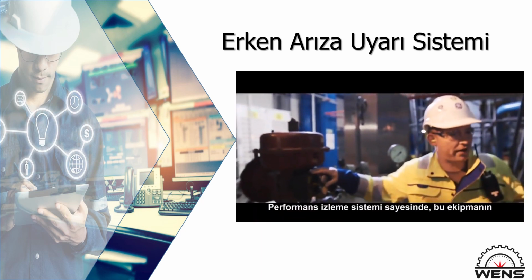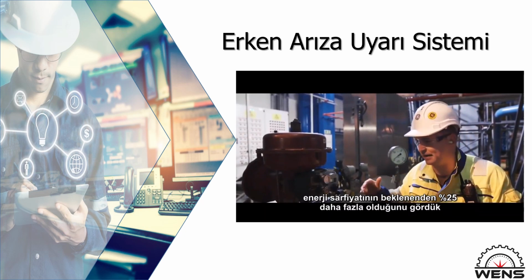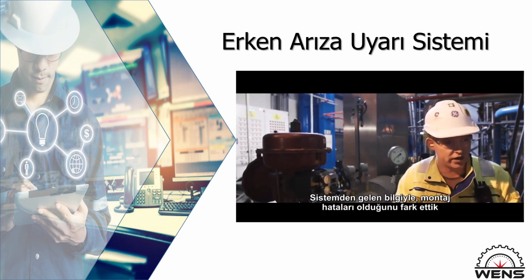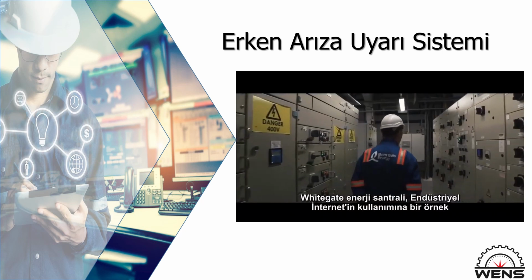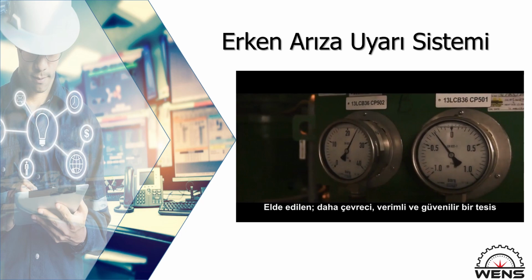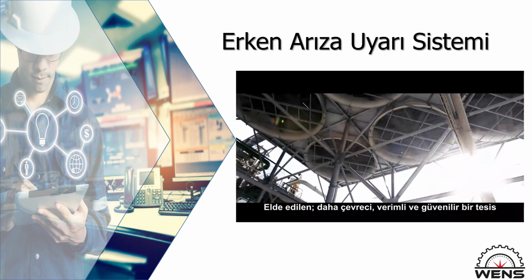Through the performance monitoring, we're able to see that we were using about 25% more gas than what would be expected at this level of load. We found that the valve setup was actually done incorrectly, and correction of that reduced gas consumption by 25% again. It's the Industrial Internet at work. The result? A cleaner, more efficient and reliable power plant.